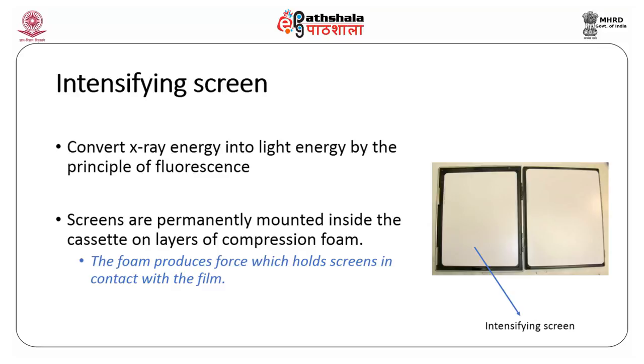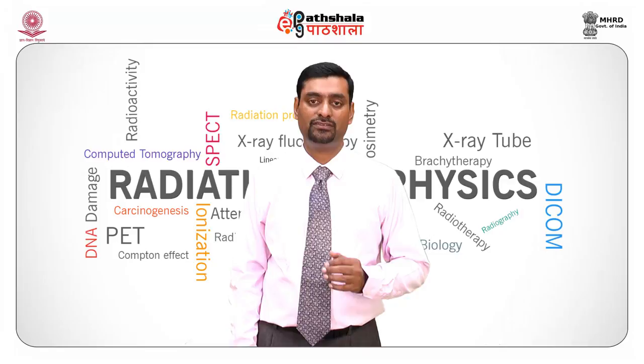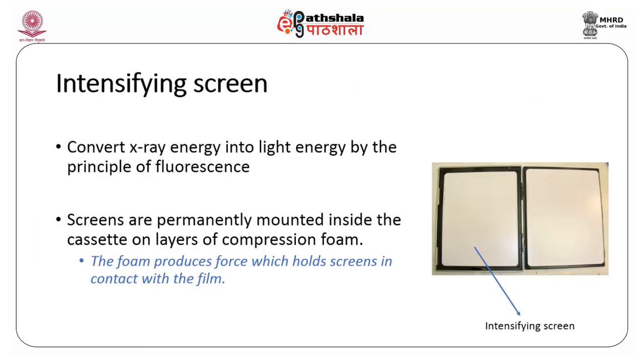Now moving on to the intensifying screen. The function of the intensifying screen is to convert X-ray energy into light energy by the principle of fluorescence. Fluorescence is when certain materials, when hit by X-rays or electromagnetic rays, produce light that stops emitting soon after the stimulus is removed. Using this fluorescent material it is possible to produce high quality images in a very short duration of time. Screens are permanently mounted inside the cassette on layers of compression foam, which produces force that holds the screens in contact with the film.